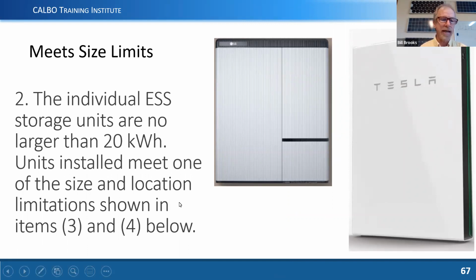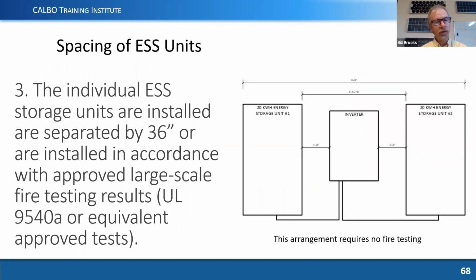Meets the size limits. Individual ESS can be no larger than 20 kilowatt hours. You'll notice that manufacturers throughout our industry have been very careful to keep residential ESS within that 20 kilowatt hour limit. These are size requirements that are currently in the California Residential Code. Individual units can be no closer than 36 inches apart unless they have large-scale fire testing. Now, large-scale fire testing usually results from UL 9540A. This is not a typo. It's an A at the end of UL 9540. It's a special set of test protocols that determine a variety of installation parameters that the manufacturer has to pass if they want to do something other than what the basic code requirement of 36 inches has.